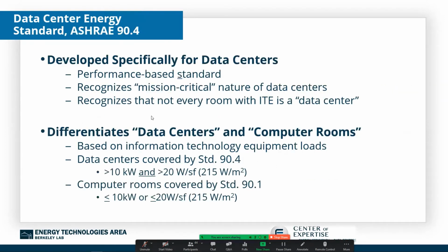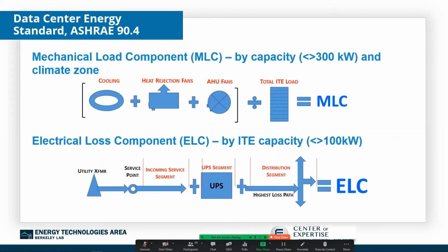Next slide. So in, I believe, 2013, ASHRAE engineers began working on data center energy standard 90.4. The first version was issued in 2016, and it's a performance-based standard. It recognizes the mission-critical nature of data centers, and it differentiates that not every room with some IT equipment is a data center—there are capacity breaks in the standard, listed at the bottom there. Essentially, data centers are defined as north of 10 kW with a power density of at least 20 watts per square foot.